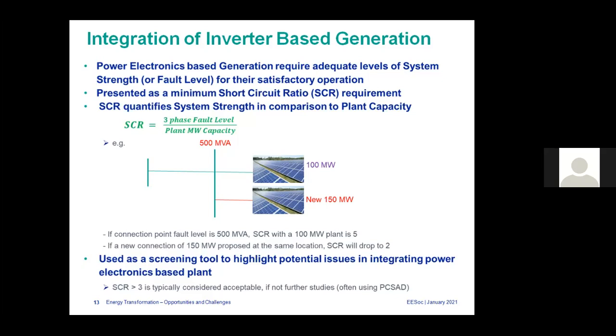This kind of assessment is presented as the short circuit ratio requirement. It's defined as the 3-phase fault level divided by the plant megawatt capacity. For example, suppose you have a 500 MVA bus bar and a 100 megawatt solar farm. We define the SCR as 500 divided by the capacity of 100, which is 5. Normally, most inverter manufacturers say that if you have an SCR of 3 or above, they expect the inverters to perform correctly under various contingency conditions.